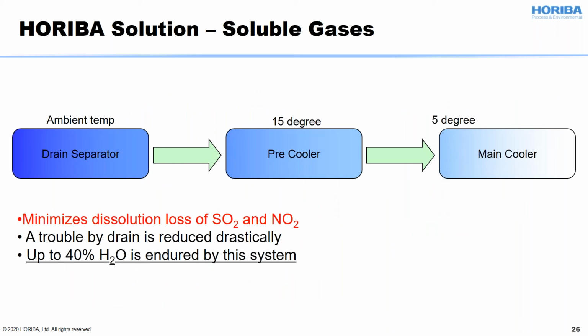So the three-step dehumidification system consists of the drain separator, the pre-cooler unit, and the main cooler. With this sampling system, we minimize the loss of SO2 and NO2. Also, trouble with drain is reduced drastically because the cooler unit does not have to deal with that much moisture at a time. So the system is durable enough to deal with sample gas which contains up to 40% moisture.